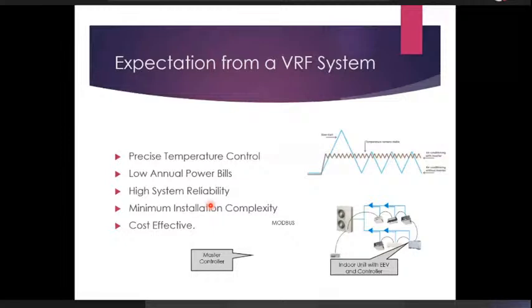And then the temperature variation. When the thermostat goes off and comes on, this blue line shows a wider variation. We can see that it is slow to bring down the temperature at first, and then there is a variation as the cycles go on and off. Whereas in an inverter system, there will be a much smaller band of temperature variation. Lower power bills because of high part load efficiency, and then the reliability of the system: because you put in so many sensors and controls, you can predict what's going to happen, and therefore to that extent preventive maintenance helps run the system longer.